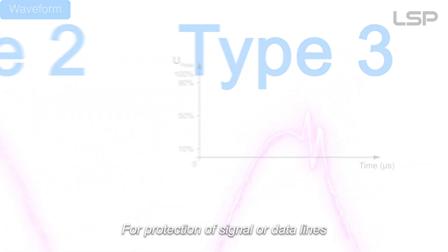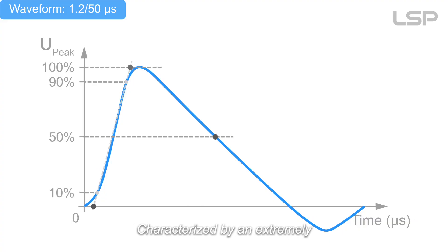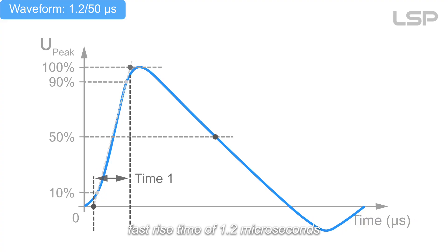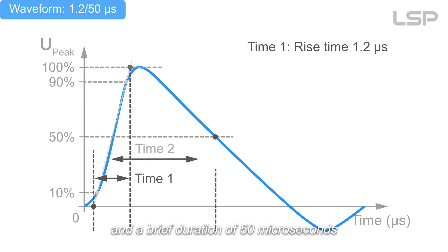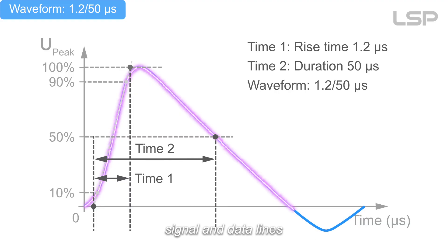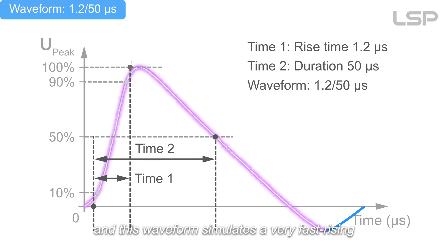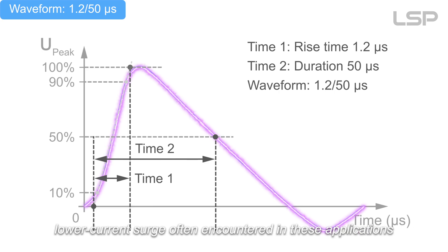For protection of signal or data lines, the 1.2/50 microsecond waveform is indispensable. Characterized by an extremely fast rise time of 1.2 microseconds and a brief duration of 50 microseconds, this waveform is utilized in defining the ratings of SPDs designed for safeguarding signal and data lines. Signal and data lines are highly sensitive to rapid voltage changes, and this waveform simulates a very fast-rising, lower-current surge often encountered in these applications.